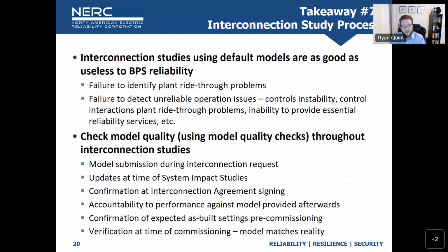Takeaway 7: interconnection studies using default models are, in my mind, as good as useless for reliability. You're not going to pick up things like failure to ride through disturbances, unreliable operation issues like controller instability or controller interactions, or the inability to provide essential reliability services like voltage control. You miss those things when using genericized or standardized models that don't reflect the as-built facilities.